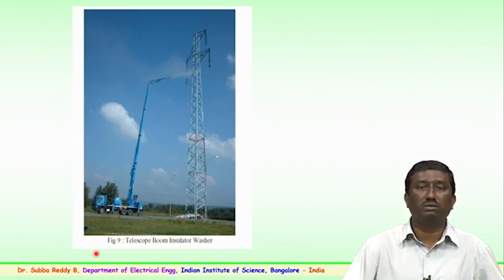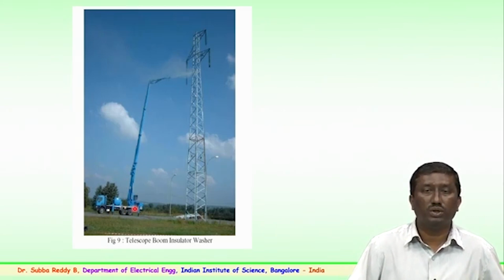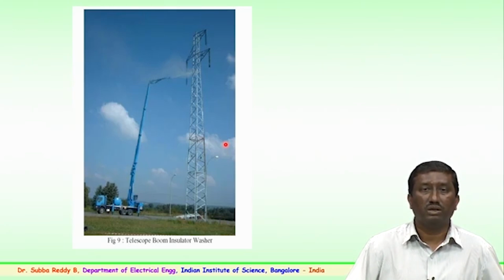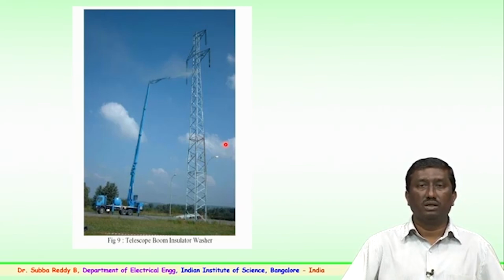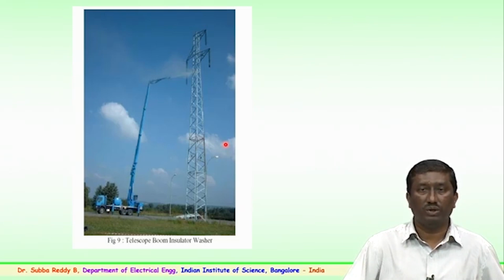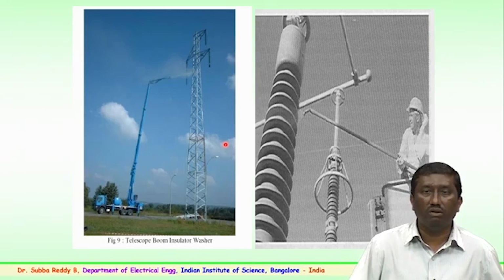So, one among them is what you see here, the telescopic type of jet mounted on a truck, which is used to wash or clean the insulators. This telescopic arrangement with a water jet works at a particular conductive level and tries to clear the insulators, so that the contaminants deposited over a period of time are removed, and particularly during pre-monsoon conditions the flashover of insulators does not happen. Again, this is a live line arrangement.